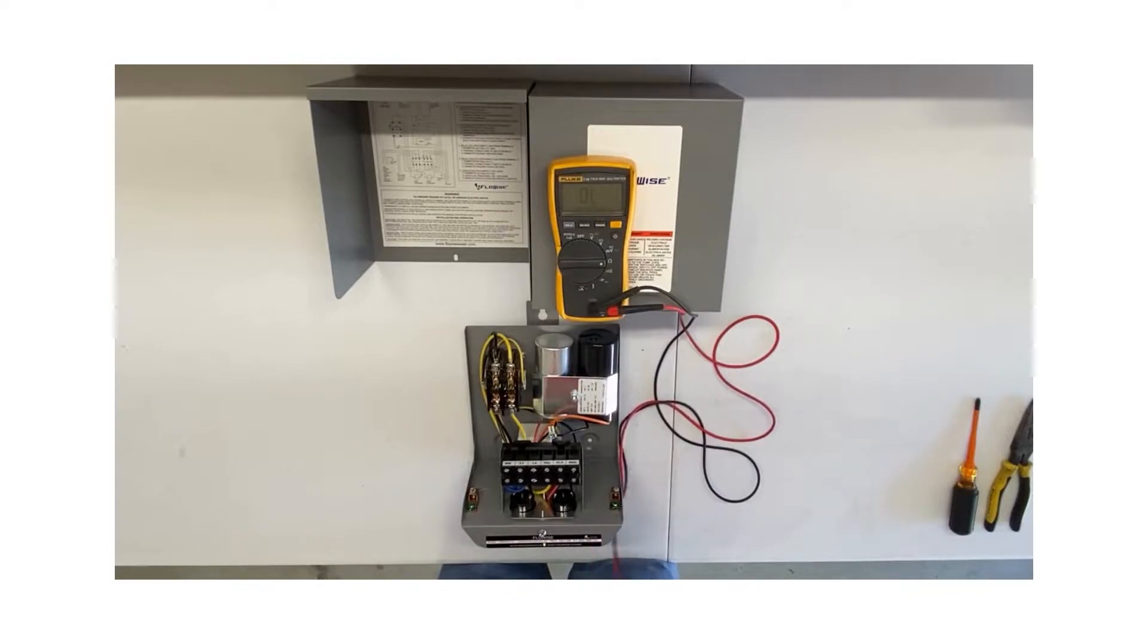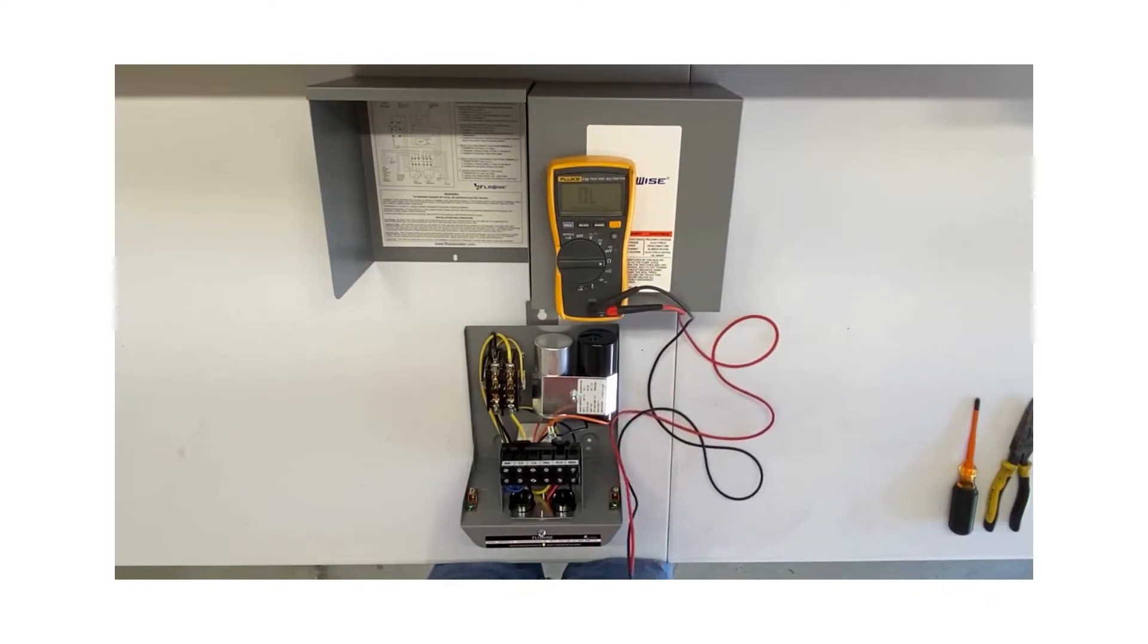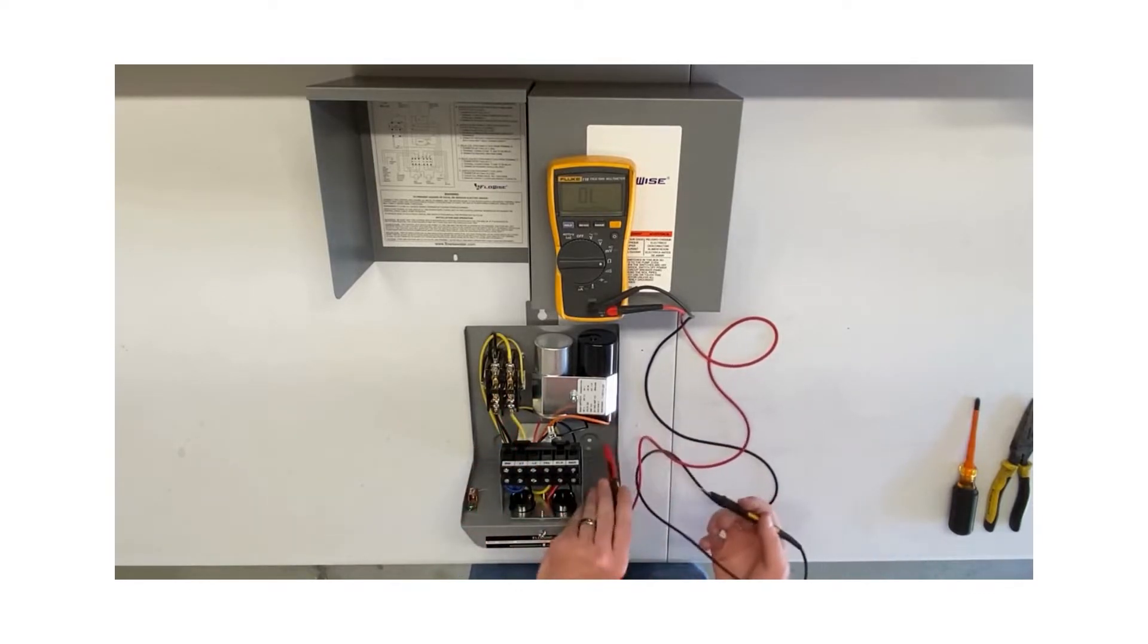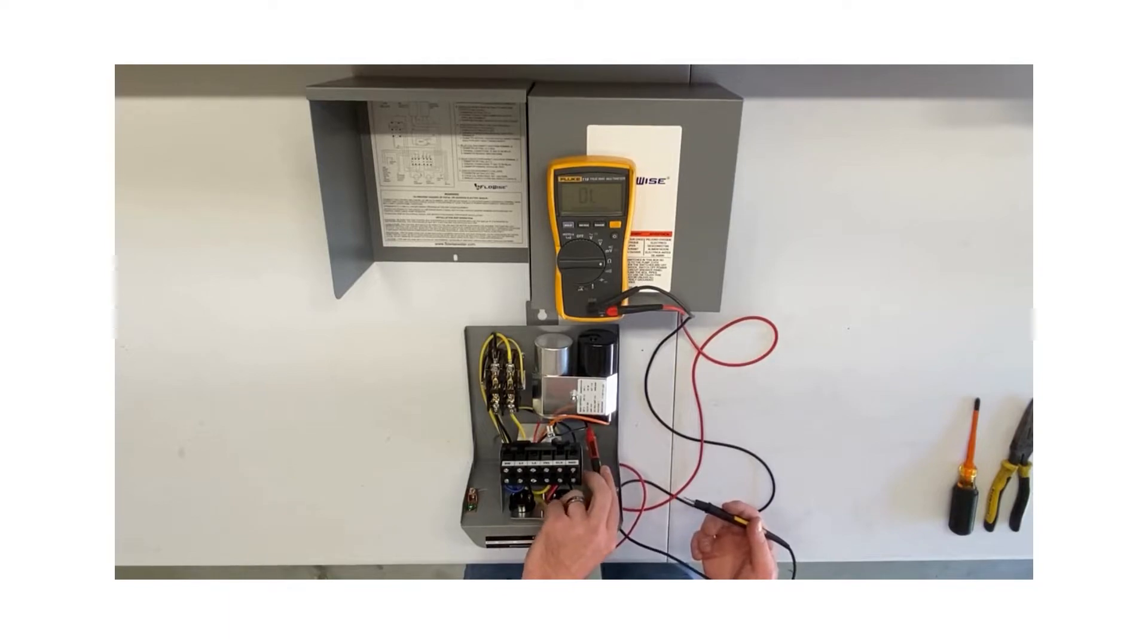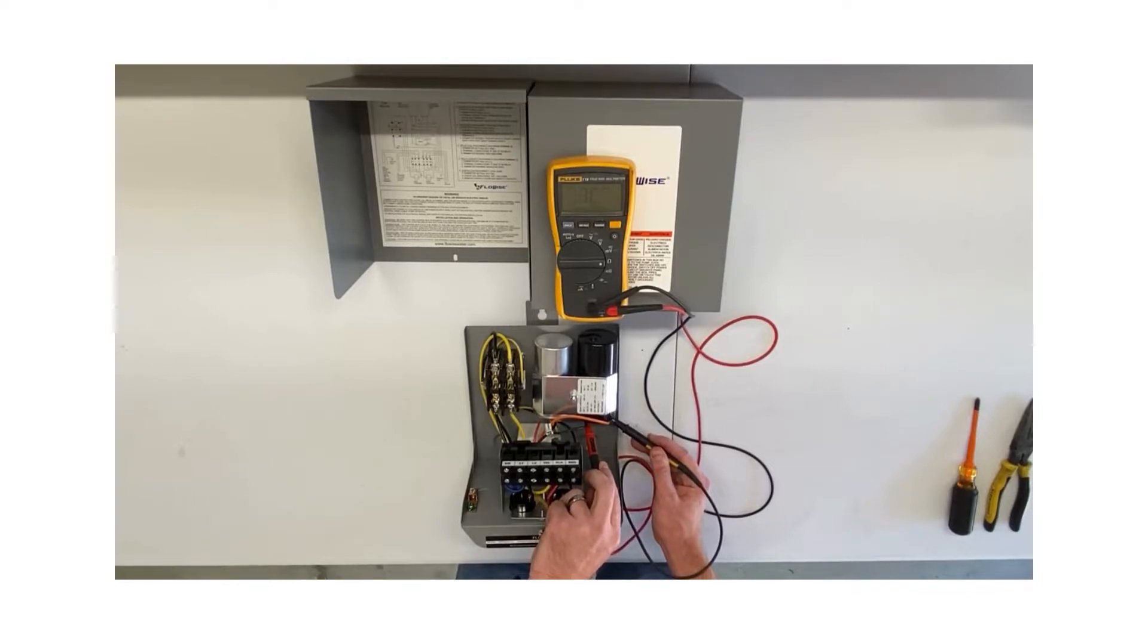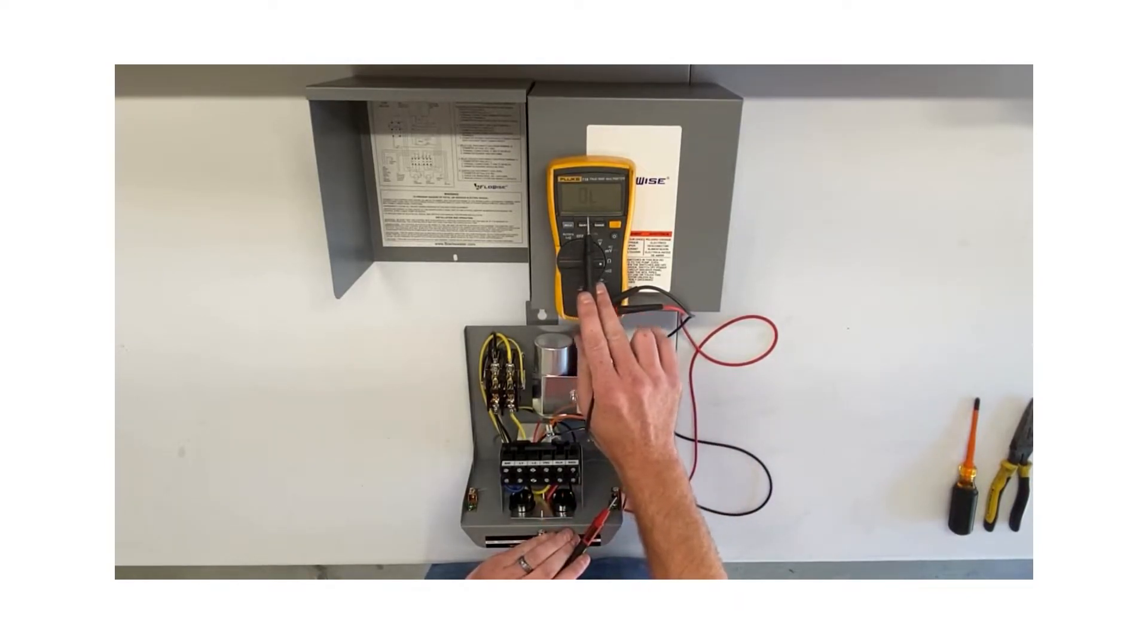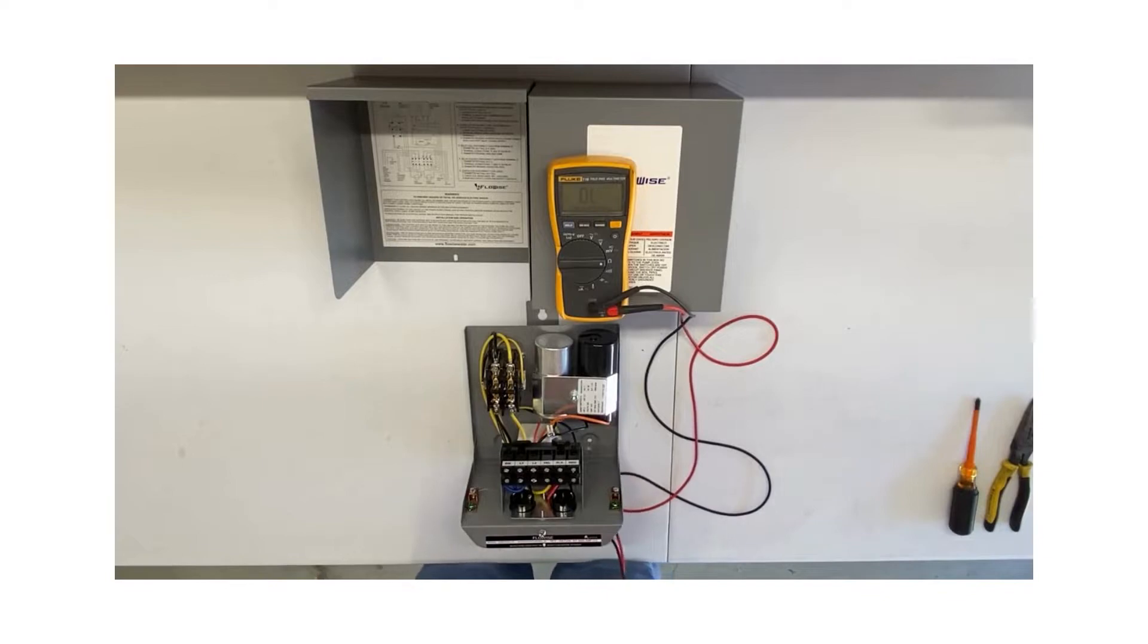With the meter still set on ohms, I'm going to press the button until I get to thousands, K ohms. If you're using an analog meter, you're going to be at R times 1000. I'm going to take one lead and touch to one post on one side of the capacitor and the other lead to the opposite side. It started really low, climbed until it maxed out, and then went to OL—over limit. The manufacturer says if you're using an analog meter, the needle should swing to zero and swing back towards infinity. That's what our digital meter just did. That's equivalent to infinity, so we know that capacitor is good.